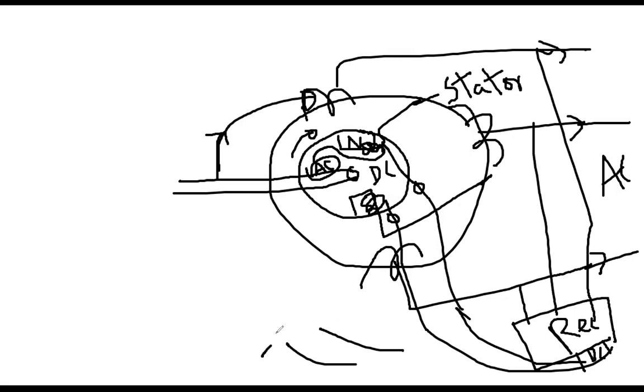These brasses are attached to the plus terminal and minus terminal of that DC system, the output of the rectifier system. And this thing is moving, so there are some sort of slip rings, these are called slip rings. So these things are moving with the slip ring, and these brushes are fixed. They are touching the brass, they are coming in contact with the brass. Consequently, the DC power is being supplied to the field system.